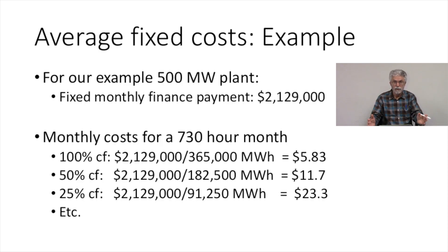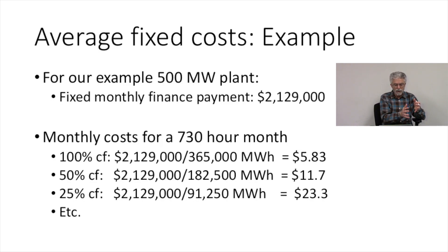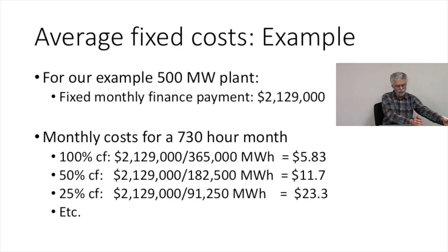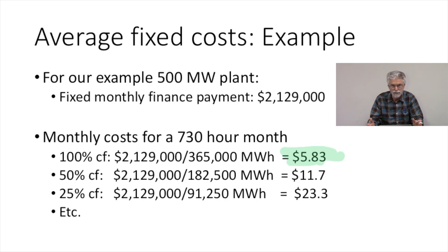A given month has about 730 hours. If our plant is running at 100% capacity factor, we have 500 megawatts for 730 hours in a month — that's 365,000 megawatt hours in a month. We take our monthly payment of $2,129,000, divide it by 365,000 megawatt hours, and we get an average fixed cost of $5.83 per megawatt hour.